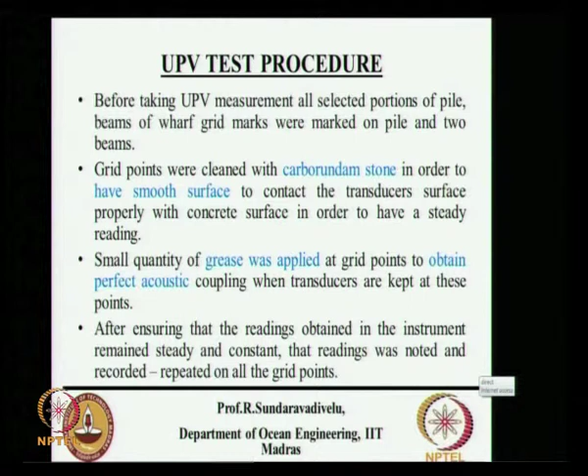So you apply a small quantity of grease at grid points to obtain perfect acoustic coupling. After ensuring that the readings obtained on the instrument remain steady and constant, the reading is noted and recorded, and repeated on all grid points. So just keep the instrument and then immediately you should not take the reading, you should keep it for a minute or so, see that the reading is steady, then you take these values.